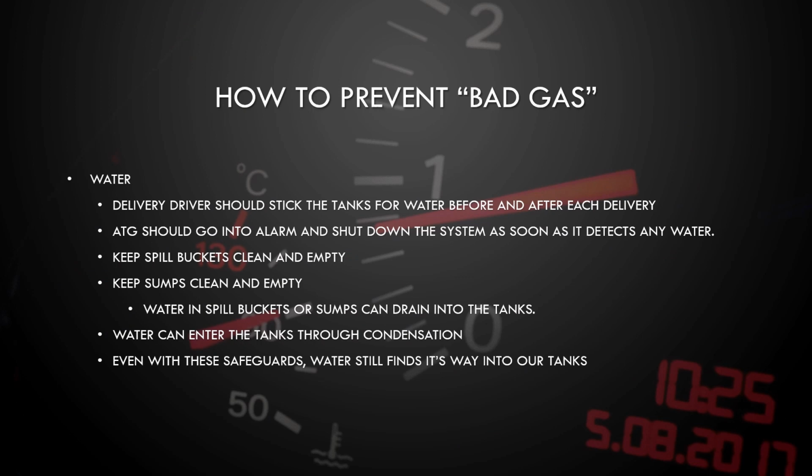Endeavor to prevent bad gas. Your number one objective should be prevent water from getting into your fuel. We do that through a variety of ways. One is our delivery processes. Whenever delivery drivers deliver fuel, they should stick the tanks for water before they deliver to make sure there's no water, and then after they deliver to make sure they didn't deliver any water.